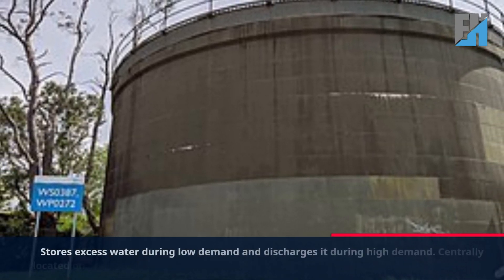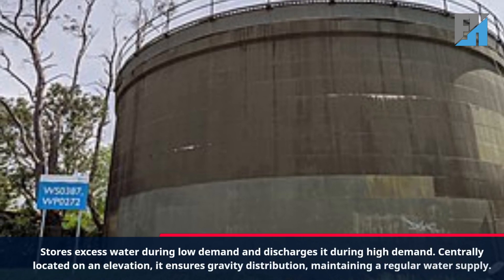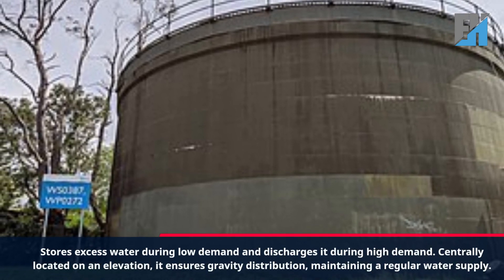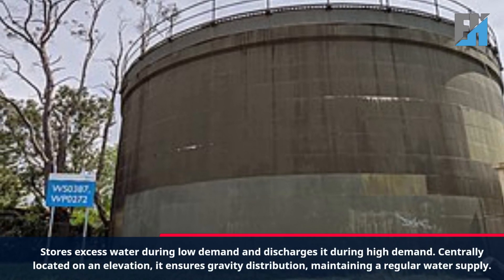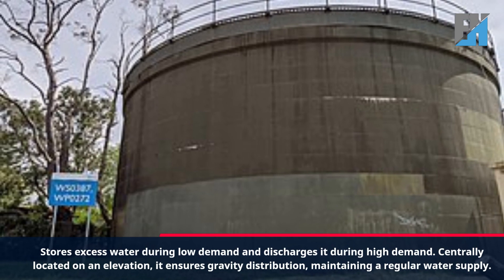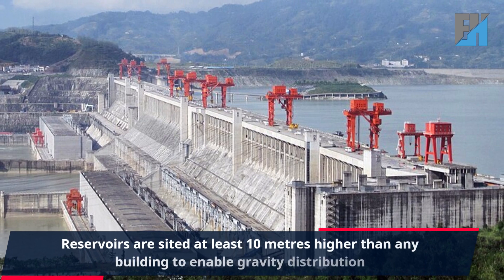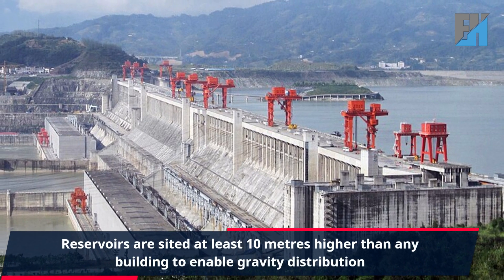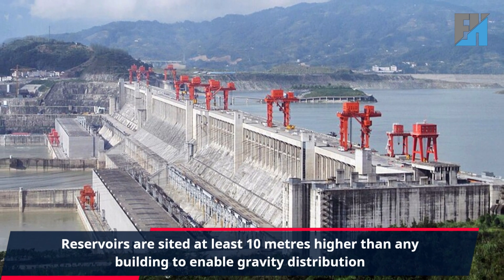The distribution reservoir stores excess water during low demand and discharges it during high demand. Centrally located on an elevation, it ensures gravity distribution and maintains a regular water supply. Reservoirs are sited at least 10 meters higher than any building to enable gravity distribution.